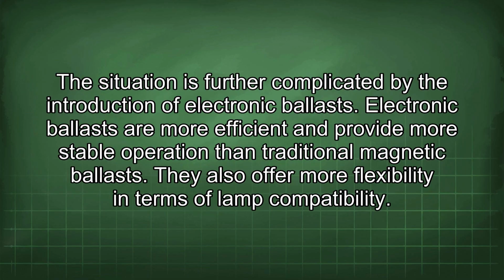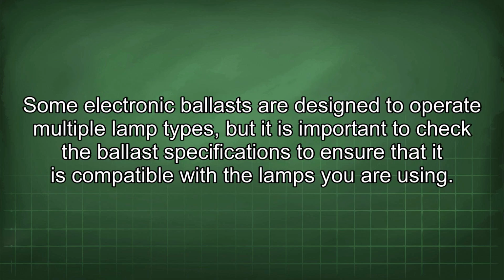This situation is further complicated by the introduction of electronic ballasts. Electronic ballasts are more efficient and provide more stable operation than traditional magnetic ballasts. They also offer more flexibility in terms of lamp compatibility. Some electronic ballasts are designed to operate multiple lamp types, but it is important to check the ballast specifications to ensure that it is compatible with the lamps you are using.